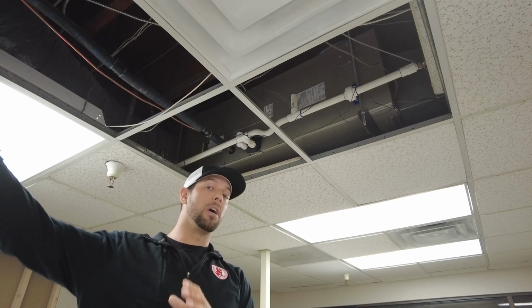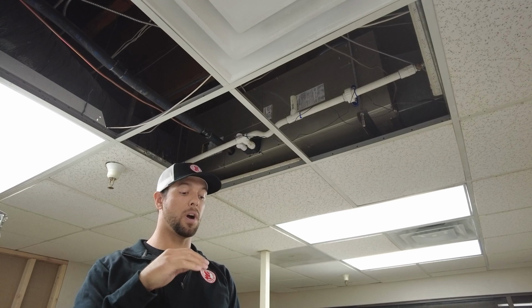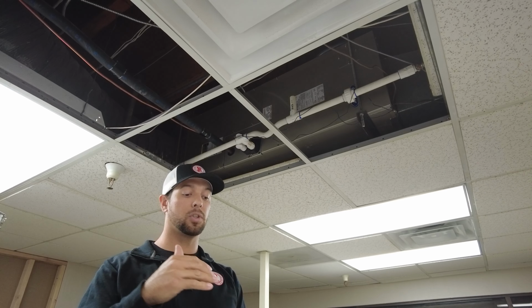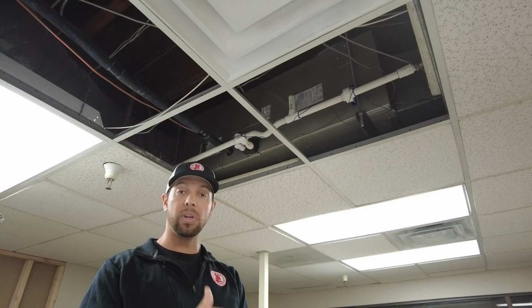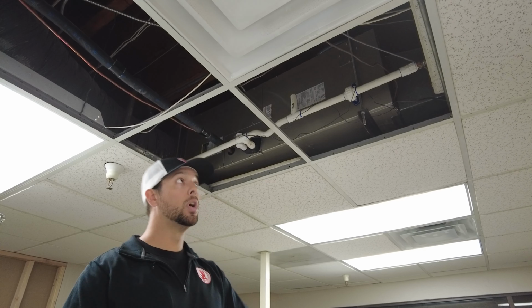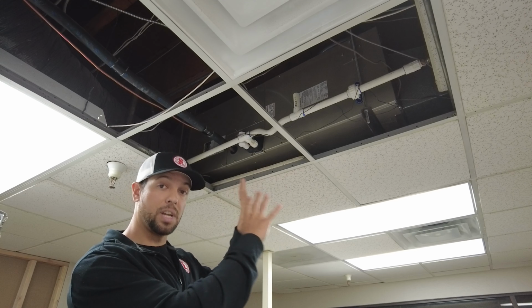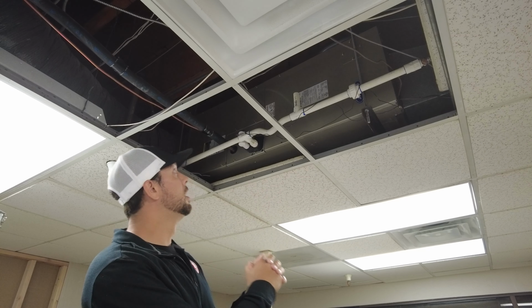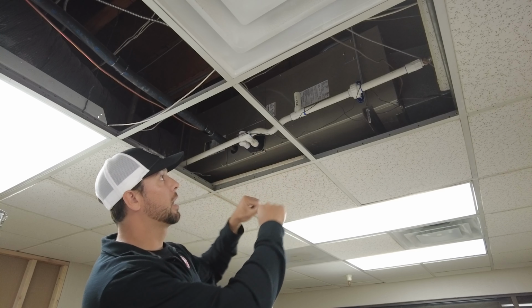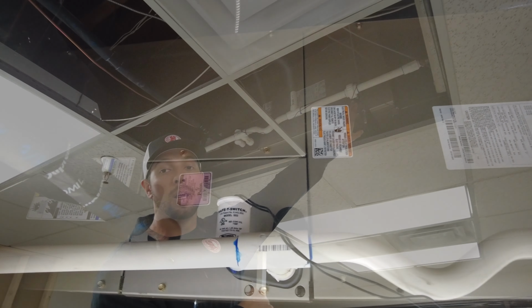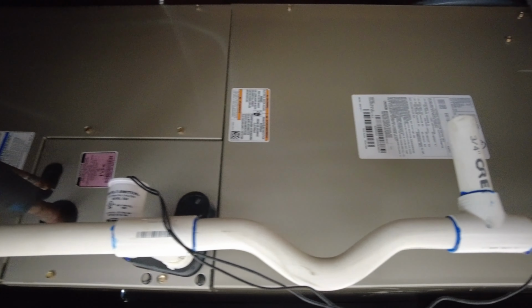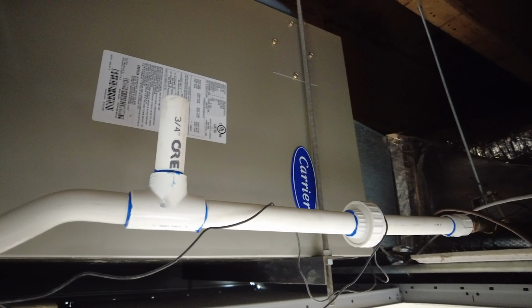After we've done that portion of our inspection and gotten the condition of the condensers, and gotten everything we need for our HVAC schedule, we want to come here as well. This is the second portion of that same inspection. So now we're looking at this air handler. We want to make sure it's the same manufacturer as well as the same date and size capacity, because it has to be compatible with the unit that's outside.